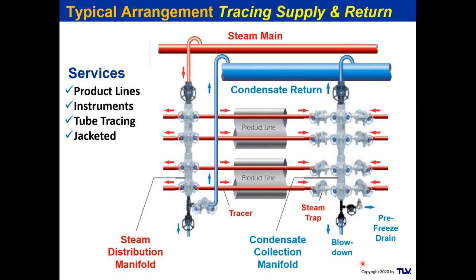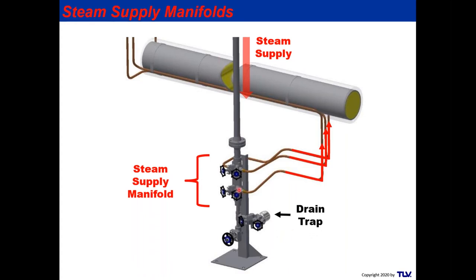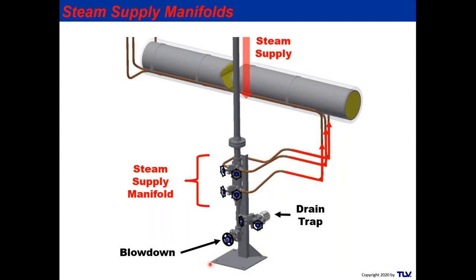Looking more closely at the steam supply manifold: steam comes off the main header down to a supply distribution manifold feeding individual tracing circuits. Since steam will be condensing in the manifold — similar to a drip application — we need a drip trap here to remove condensate so it doesn't back up into the tracing system. A blowdown is also included so that any dirt and debris captured in the assembly can be cleared frequently.